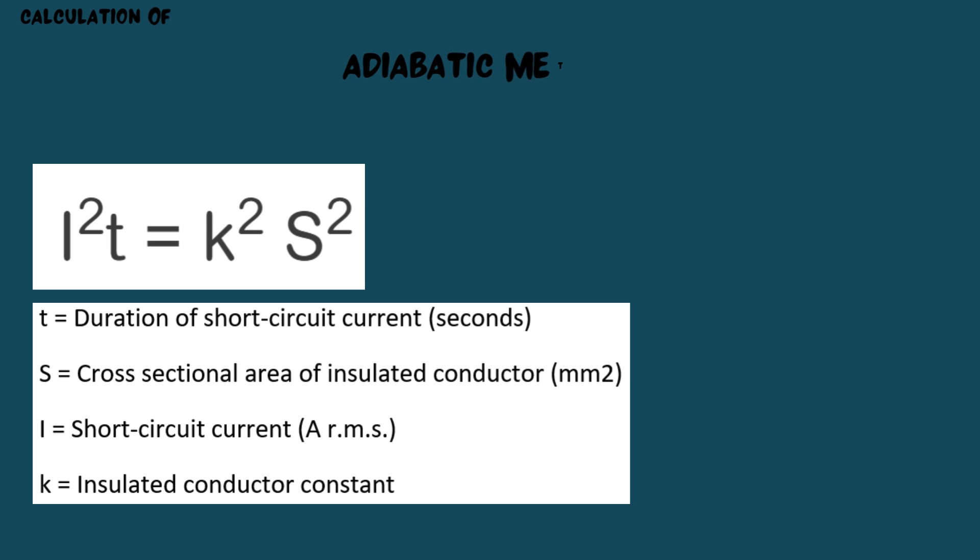The adiabatic equation shown is used to calculate the minimum cross-section of the cable during a short-circuit. T represents the duration of short-circuit current in seconds. S represents the cross-section area of the insulated conductor in square millimeters. I represents the short-circuit current, and K represents the insulated conductor constant.